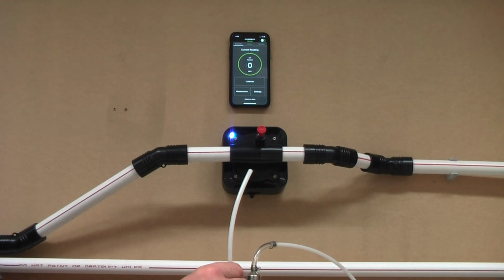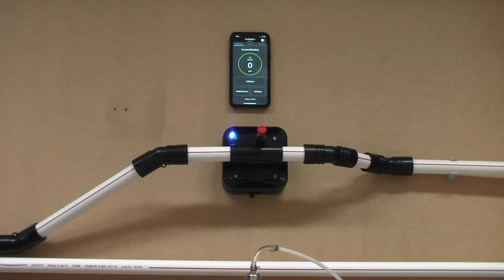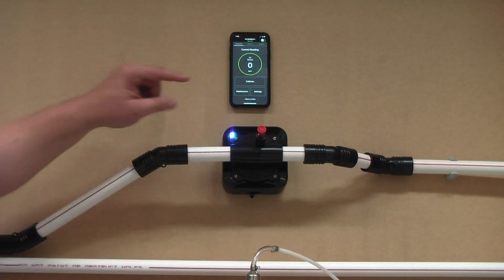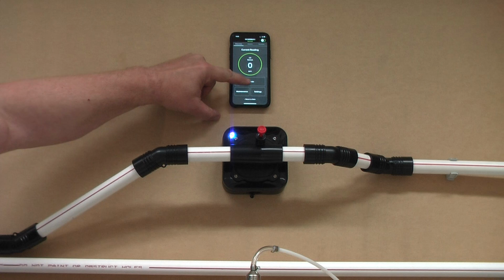So to perform the test, I need to make sure that there's no flow going through the pipework to the gas detector. So I do this by either turning the detector off, by removing power, or placing the detector into standby mode. Once this is achieved, I can initiate the calibration process by pushing calibrate here on the app.